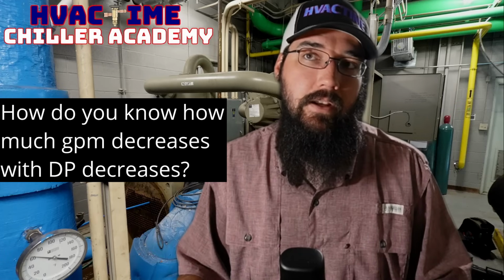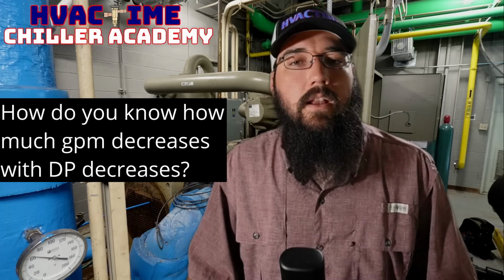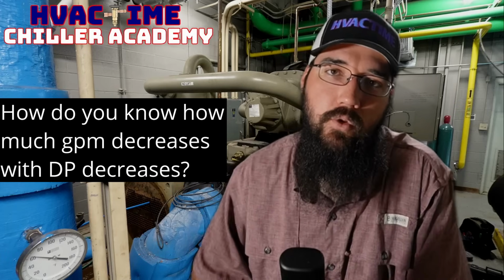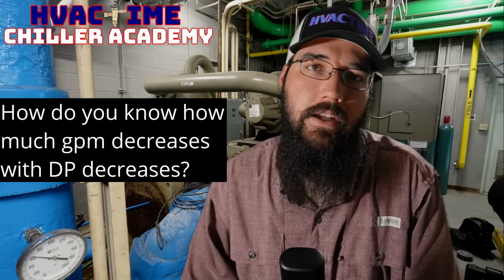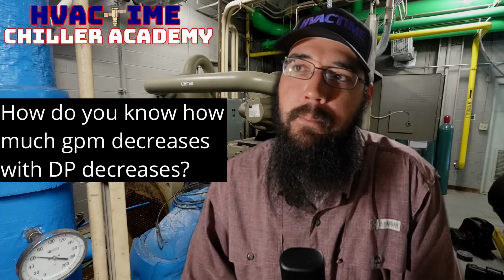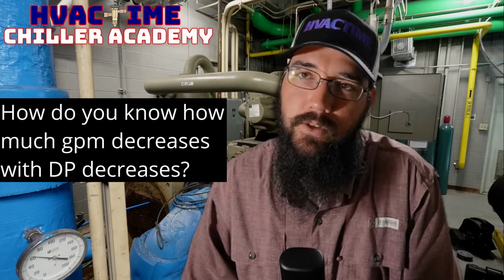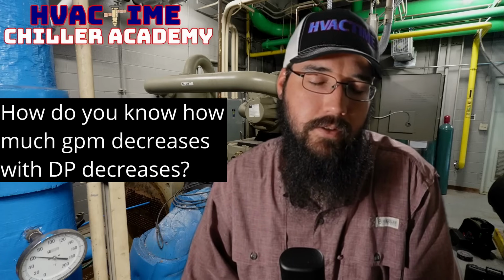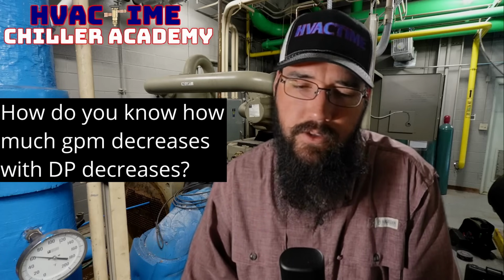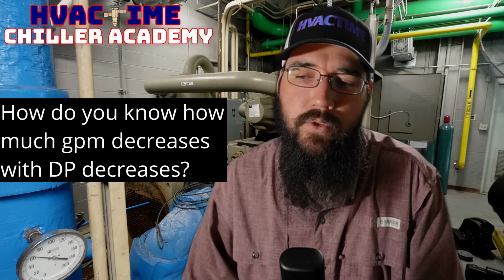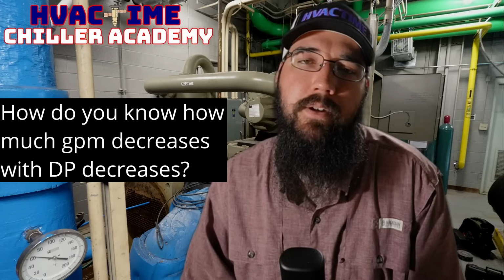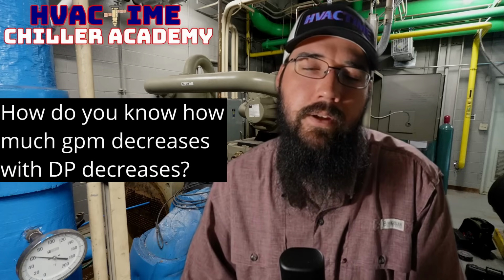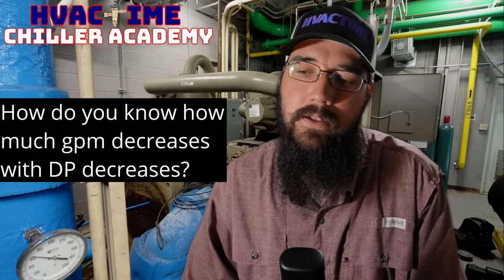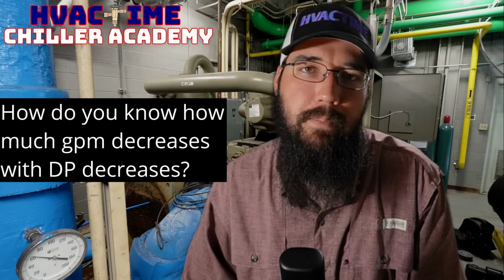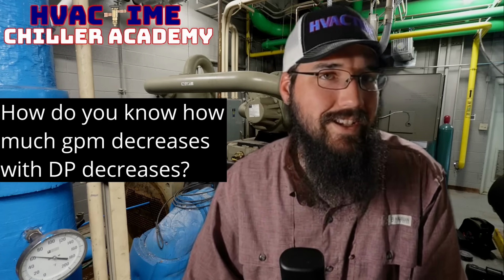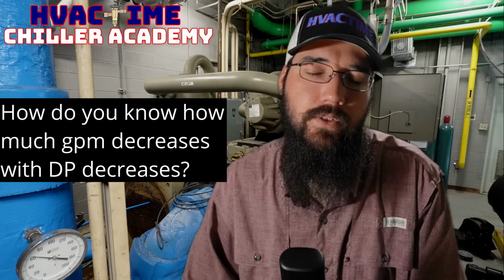That's probably one reason why chillers are so challenging on the flow side—they're not mass produced in the same way, especially water cooled centrifugal equipment. They're not mass produced like RTUs and other stuff. Maybe air cooled equipment is different; we definitely have much better flow data on air cooled equipment that's far more of a copy-paste template design. But that's just not true for a lot of these centrifugals and stuff.